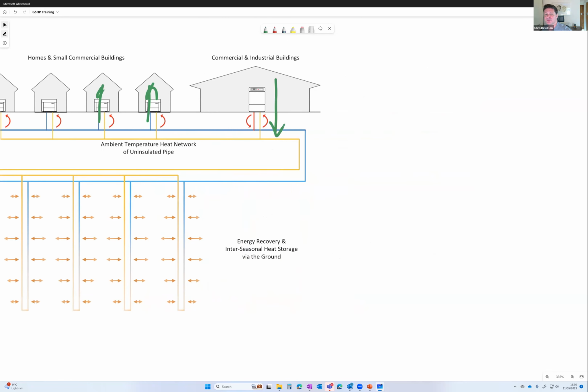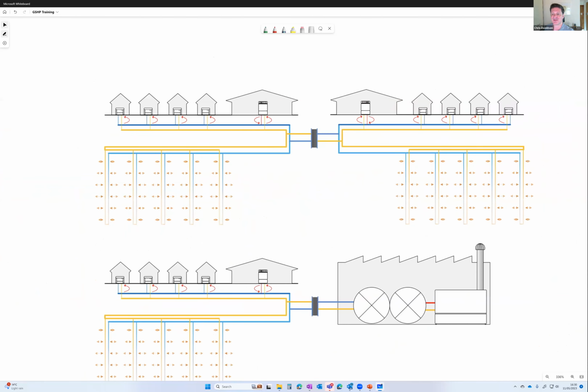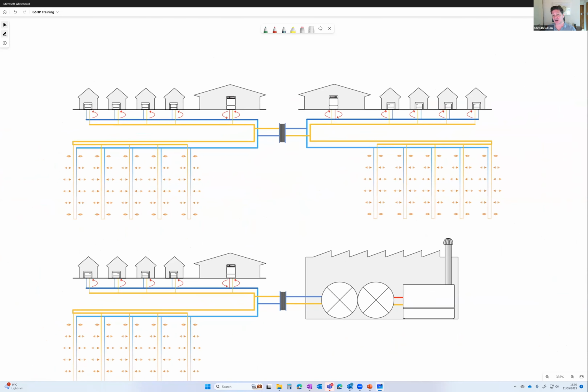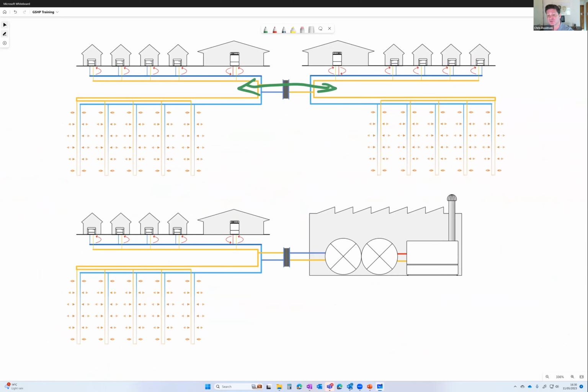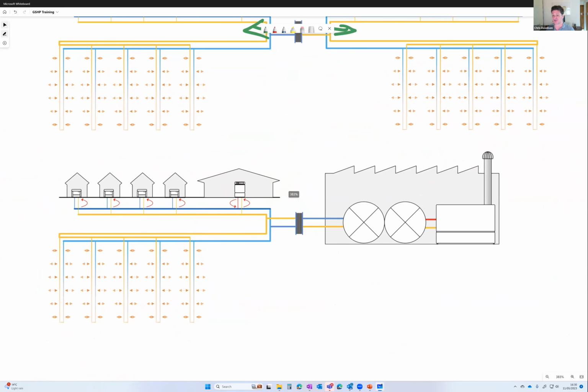What you can actually do beyond that is start connecting these heat networks together. So we might have two ambient heat networks here, put a heat exchanger between the two, and heat will naturally balance between those two networks. We could also consider any other source of heat, as I was saying earlier - this might be a waste to energy plant, a conventional second, third or fourth generation heat network, or an industrial process, for example - and we can just put heat into that low temperature network.